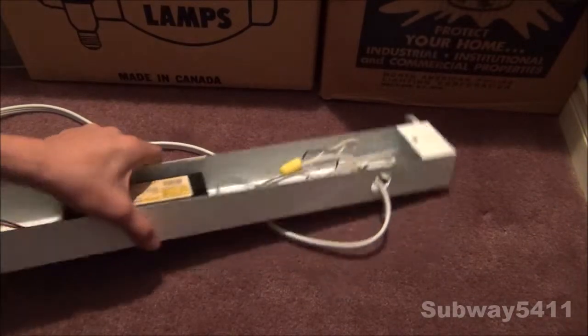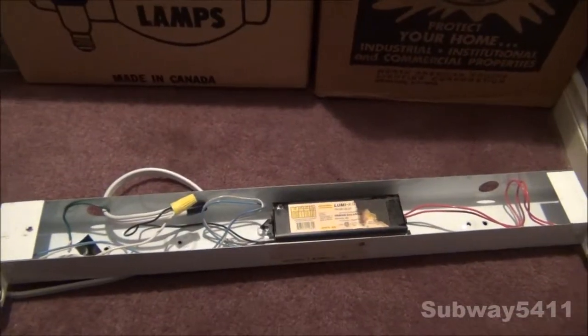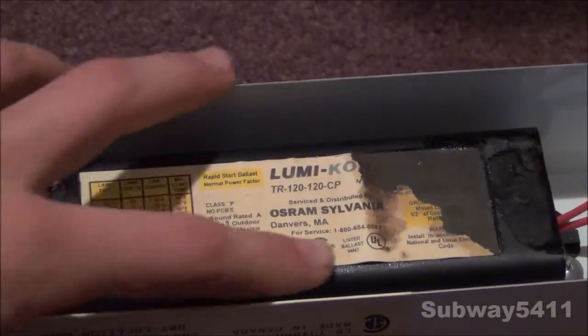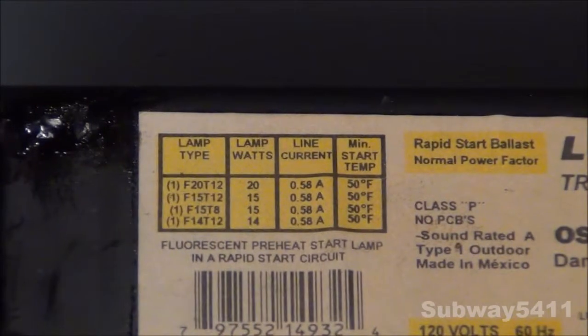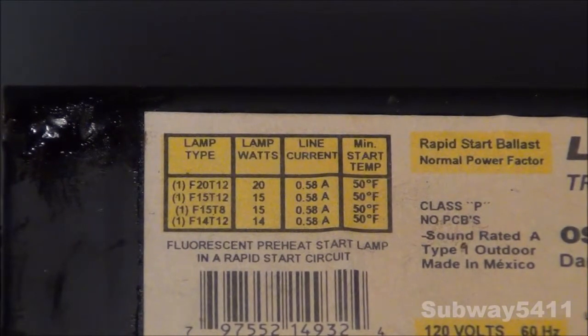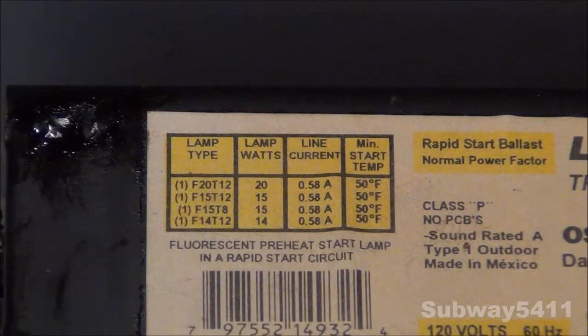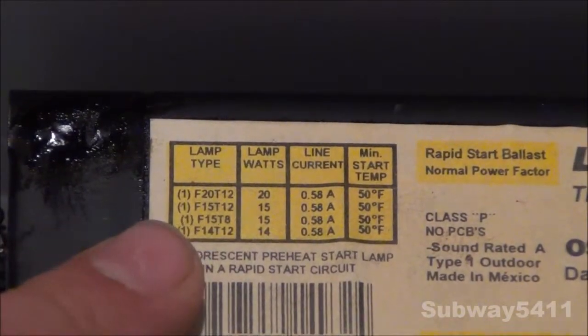We can see the ballast inside — it's made by Osram Sylvania, a Lumi-Kon ballast distributed by Osram Sylvania. If you can get a zoom in on this chart: we can see that it can take 20, 15, or 14-watt bulbs. The 20-watt bulb has to be a T12, apparently, but a 15-watt can be either a T12 or a T8.